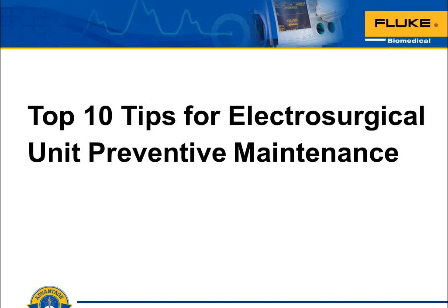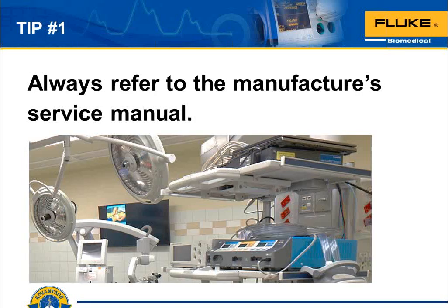So armed with an understanding of the potential risks and where the requirements for testing come from, let's transition to the top 10 tips for electrosurgery unit preventive maintenance. And it does include electrical safety. So let's start with tip number 1. Always refer to the manufacturer's service manual. Manufacturer recommended test procedures should always be followed.